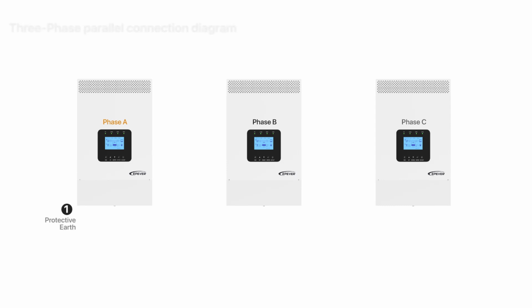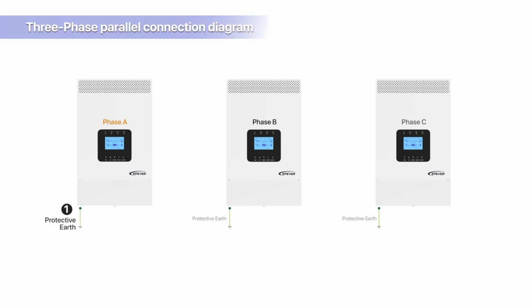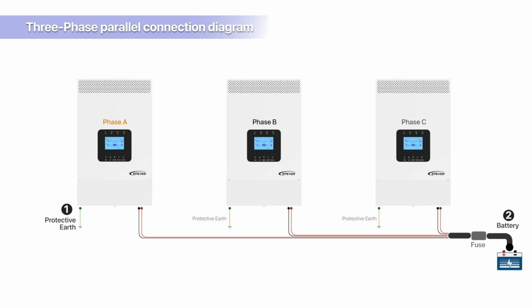Protective earth connection. Start by connecting the protective earth wire to each device individually. Battery bank connection. Connect all devices independently to the same battery bank. It's important that the wire gauge and length from the battery bank to each inverter are identical to ensure uniformity.